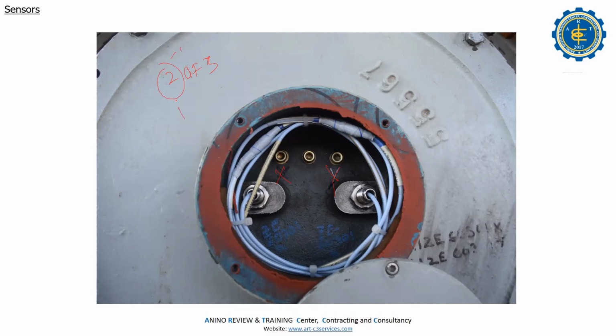If only one does, it will not trip. Here in our System 1, even if only one hits alarm, it will trip. This is the new one. That is the old, 2 out of 3.